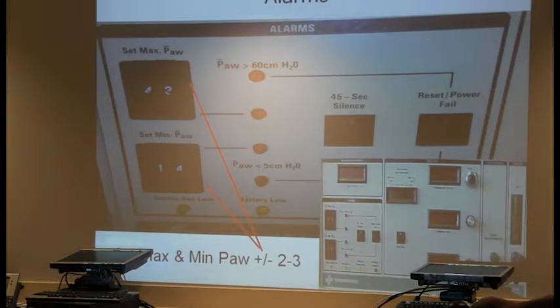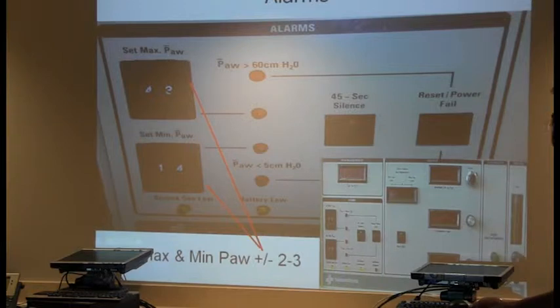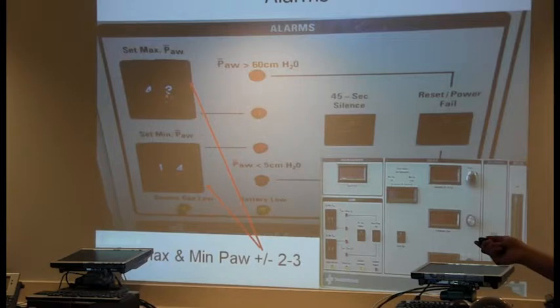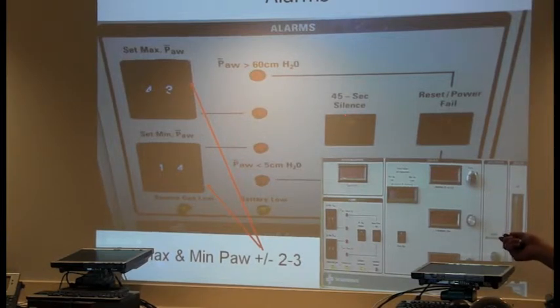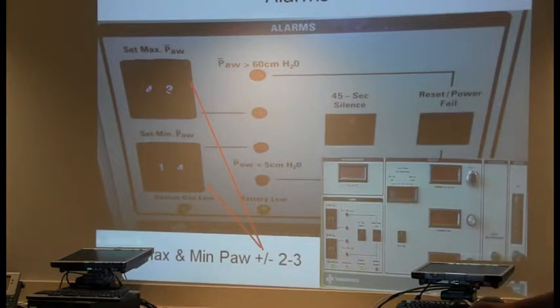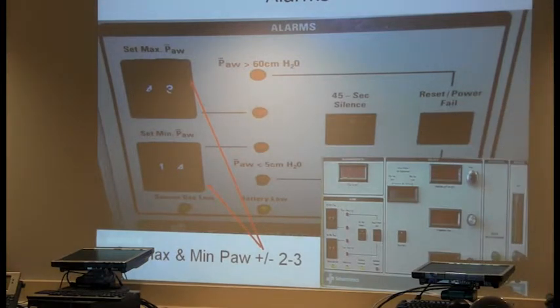So let's talk about the alarms. So alarms. Set max and set minimum, okay? In the NICU, 2 to 3 above. Adults, you can go 3 to 5, plus or minus 5 in adults because the ranges are so much higher, okay? A couple things here you see is that you have your silence button, okay? So when the vent alarms and you know what it is, fix it please and hit the silence because it's such an annoying alarm and everyone's gonna look at you, ding, ding, ding, like a truck backing up, and then the longer it goes, like, okay, hello. So to divert away from the attention, just hit the silence, okay?